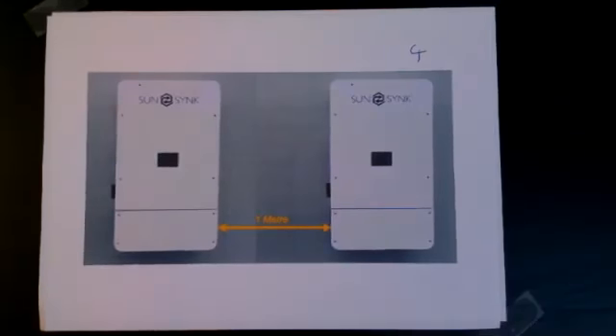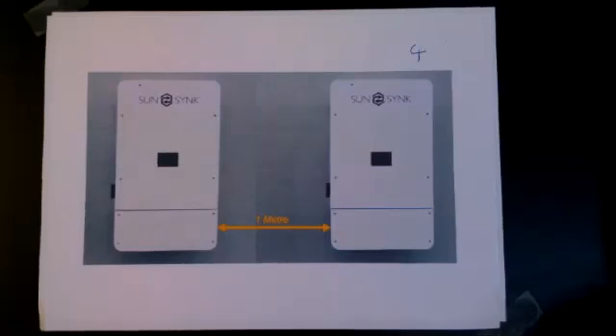The mounting of the inverter is important because there are ventilations at the side of the inverter. So if you're going into parallel, try to keep them apart, especially if you're in a hot environment. So it's quite important to keep the distance between the inverters. We always recommend a meter.